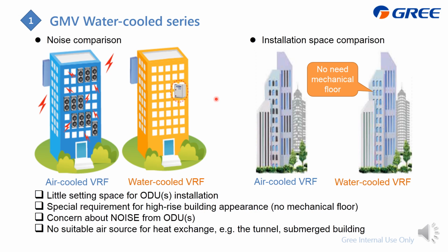And this is the comparison to the air cool series. First is the noise comparison. As you can find, for the air cool there must be fans, so the noise must be higher compared with the water cool. On the other hand, for the water cool, we don't need a special service floor. We just need a special small size service room. An airway floor is okay. And in that case, we can save space.